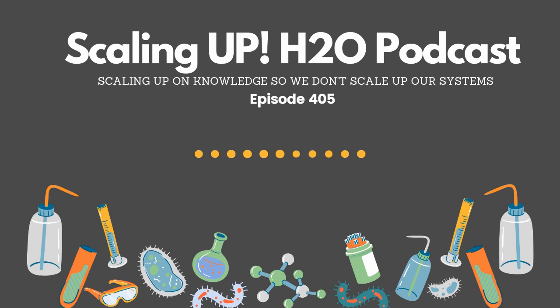Well, that was a challenge. As you said, it will depend also on season. So we have a database we started building to understand at least the highs and lows of critical components. We know, for example, that the water has high organic content and also high bacterial growth. But specific to this project, when discussing with the customer, one key component was automation - we need some kind of automation to capture any deviation in the makeup water or anything that could happen in the system, so we could go in and adjust anything in the water treatment to address that type of variation.